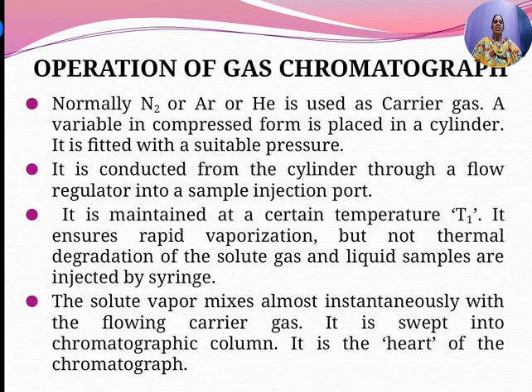The column is the heart of the chromatograph. The different solutes in the vaporized sample are separated from each other by virtue of their different interaction with the column packing. The column is packed with a specific material, so depending upon the retention time and the nature of the components, the sample will be passed on through the column. The column is maintained at a temperature T2, which determines the time for passage of the solute, and the resolution and efficiency obtained with the particular column.